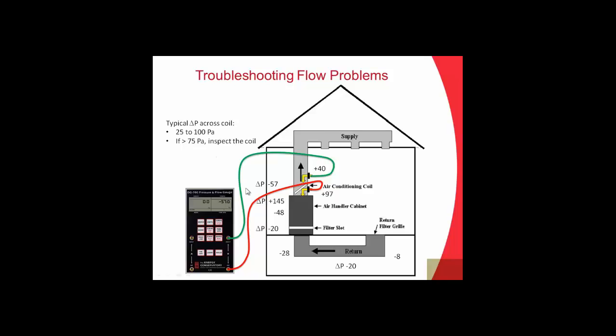If you're seeing pressures of over 75 pascals, then it's time to really get in there. If there's not an access panel, you'll want to cut an access panel on the side of the duct and check it to see how dirty it is. It may be that the furnace filters haven't been changed often enough, and when those coils have condensation on them when the air conditioner is running, they're going to collect a lot of dirt. So you're going to want to cut a hole in your duct and either remove that coil and clean it out, or do the best you can with it in place, and that may be your issue.